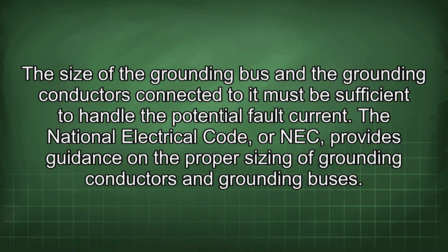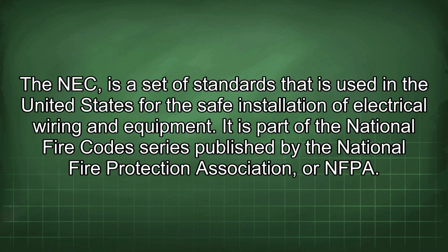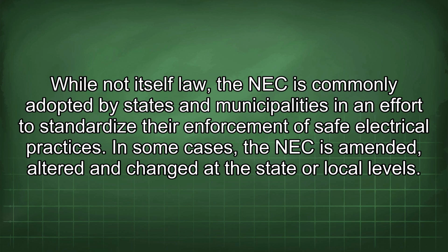The size of the grounding bus and the grounding conductors connected to it must be sufficient to handle the potential fault current. The National Electrical Code, or NEC, provides guidance on the proper sizing of grounding conductors and grounding buses. The NEC is a set of standards that is used in the United States for the safe installation of electrical wiring and equipment. It is part of the National Fire Code series published by the National Fire Protection Association, or NFPA. While not itself law, the NEC is commonly adopted by states and municipalities in an effort to standardize their enforcement of safe electrical practices. In some cases, the NEC is amended, altered, and changed at the state or local levels.